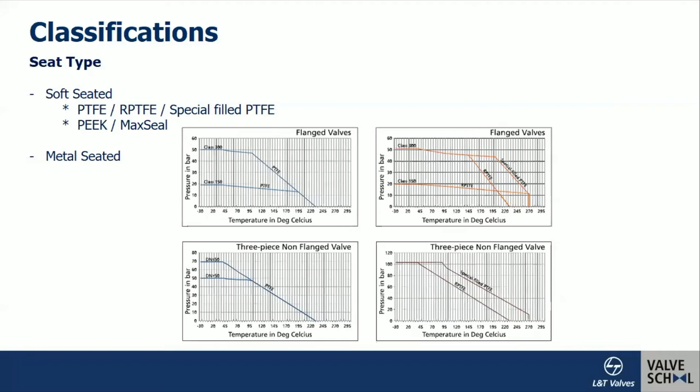Another variant is reinforced PTFE — glass-filled PTFE — which can withstand higher temperatures up to 230°C. There is also a special filled PTFE that can go up to 270°C. These three are commonly used soft seats. For higher pressure classes like Class 900 or Class 1500, a material called PEEK can be used. Max Seal is a trade name for a special filled PTFE that can be used for high-temperature applications up to 275°C.